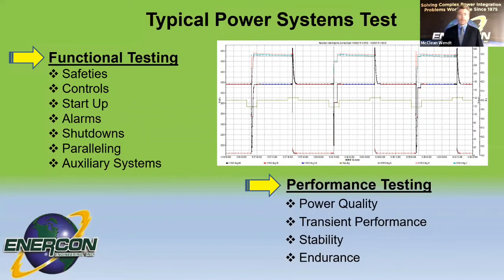Okay. So there's several different tests that we typically perform on power systems, and these are going to be governed by the design and the requirements of the customer. So with functional testing, again, we want to do any of our safety testing, any of those devices that are going to protect the equipment and personnel. We want to make sure that those are tested first and function accordingly.